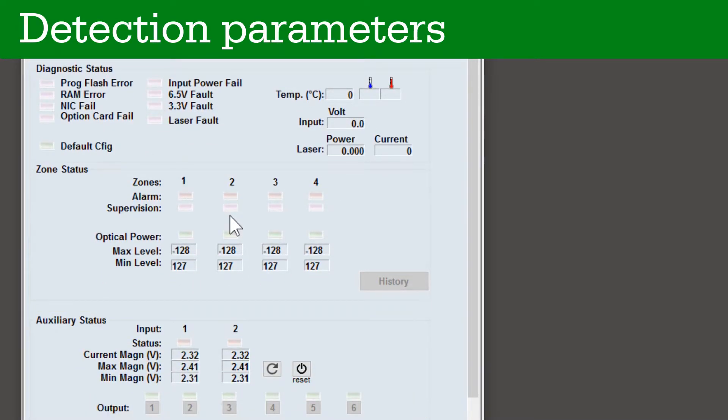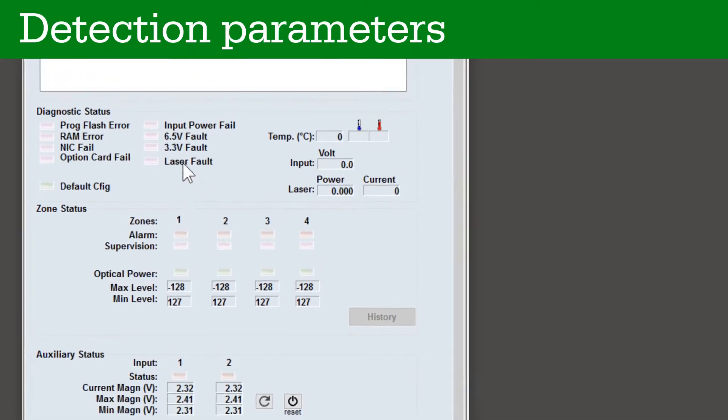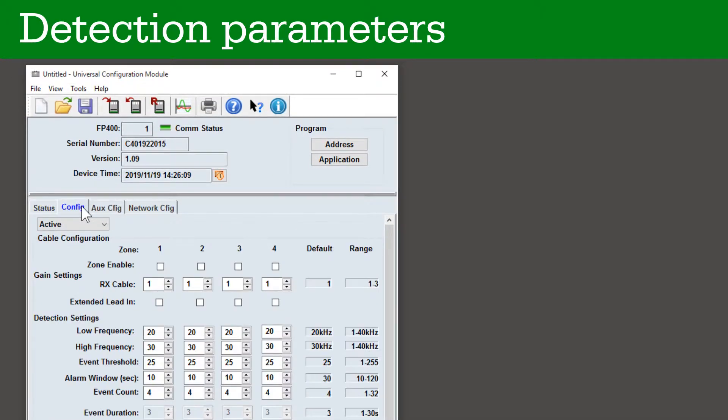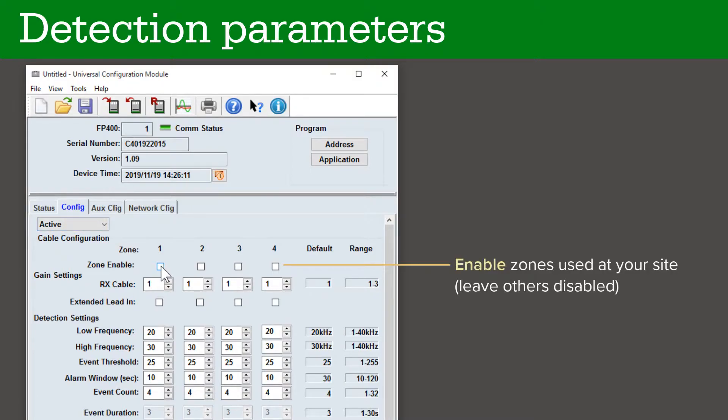The first step is to enable the detection zones and configure their settings. Click on the Config tab. Enable the zones used at your site. The zone numbers correspond directly with the RX and TX fiber connections on the back of the processor. Unused zones should remain unselected.